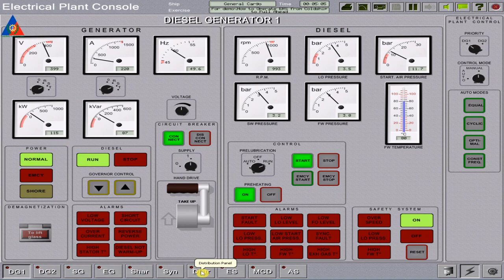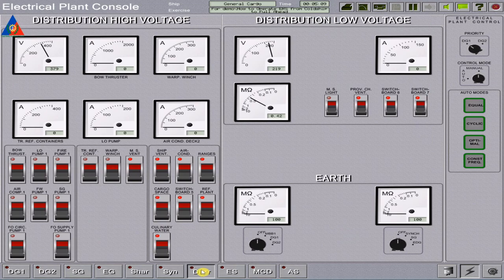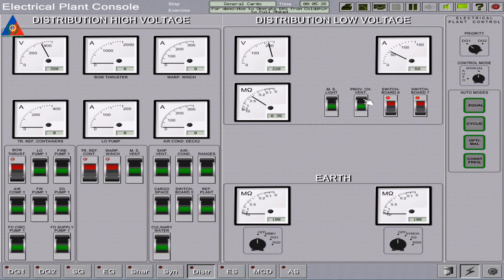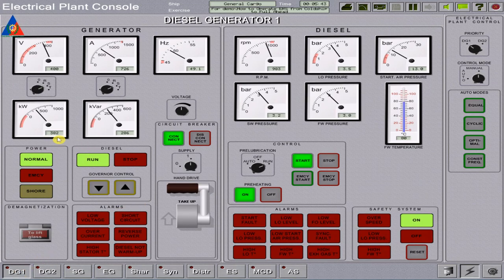Put in additional load. Go to the distribution page and turn on the switches for the high as well as low voltage distribution breakers. Note that the bow thruster circuit breaker should be off because we need two diesel generators in order for it to be utilized. If the electrical load is normal, stop the preheating of generator number one and set the pre-lubrication to automatic setting.